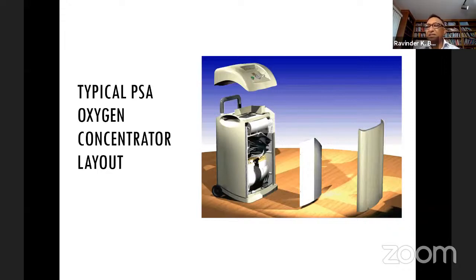The consideration and design are exactly the same. The only difference is that in a concentrator, you're trying to reduce the weight. Also, since it sits next to the patient, it has to be very quiet, and making it quiet is a big issue. You put in lots of foam, but then you retain a lot of the heat of compression within the cabinet, which is harmful. So there's an optimization between the practicality of the process, the quietness of the system, and the size of the system, but the underlying design is the same.